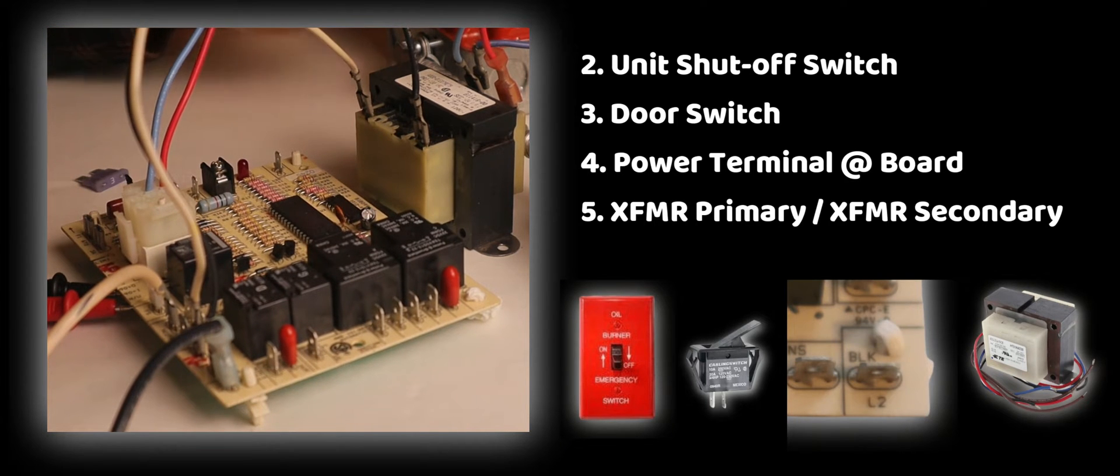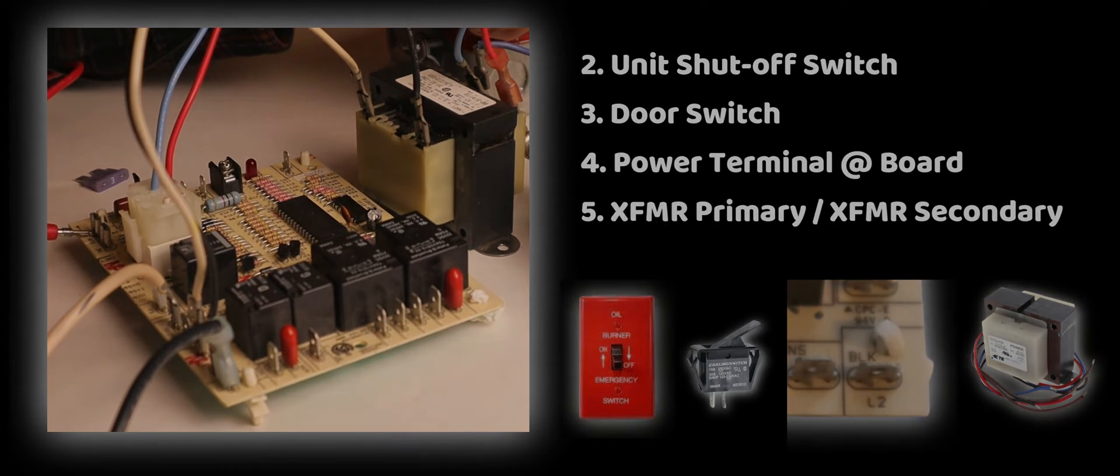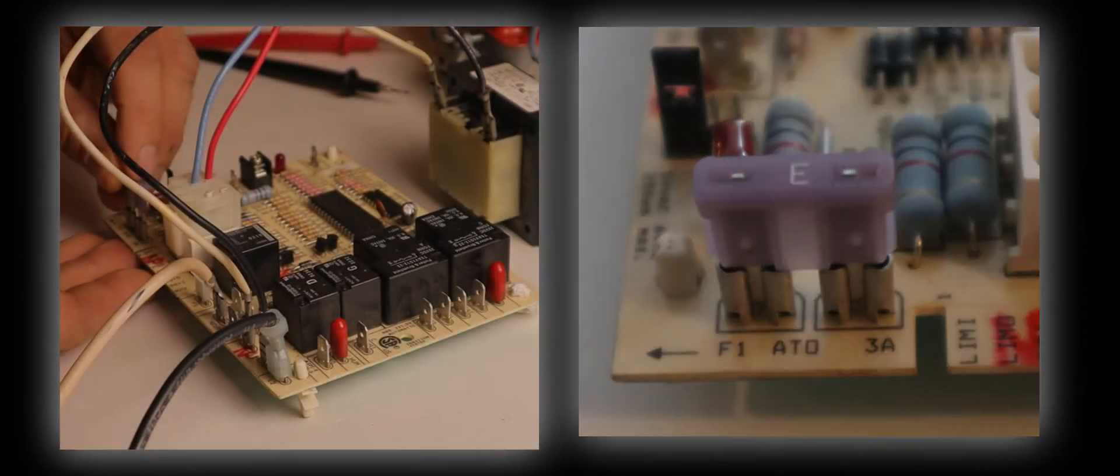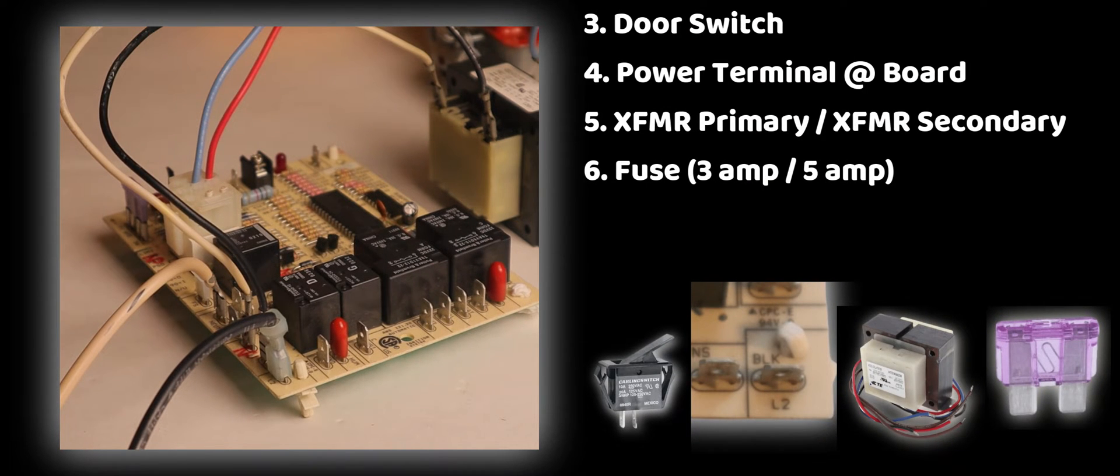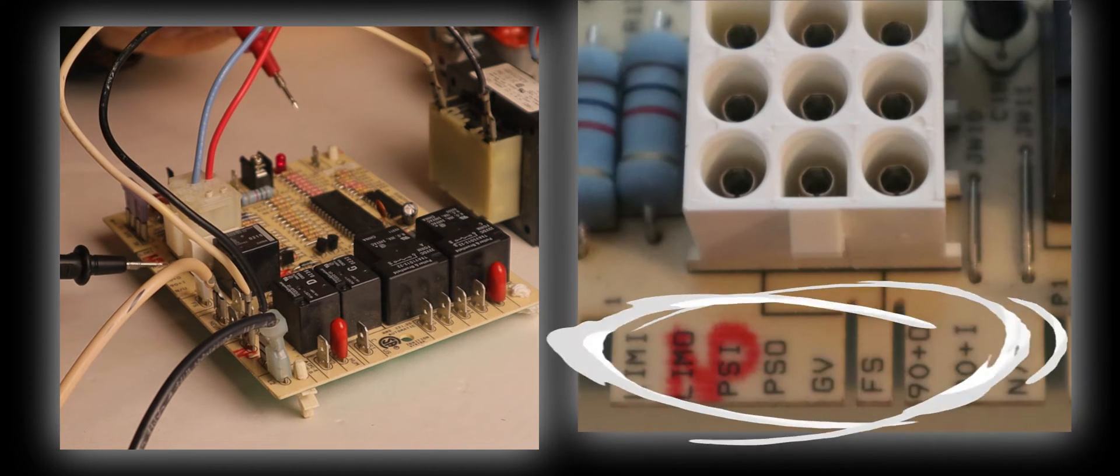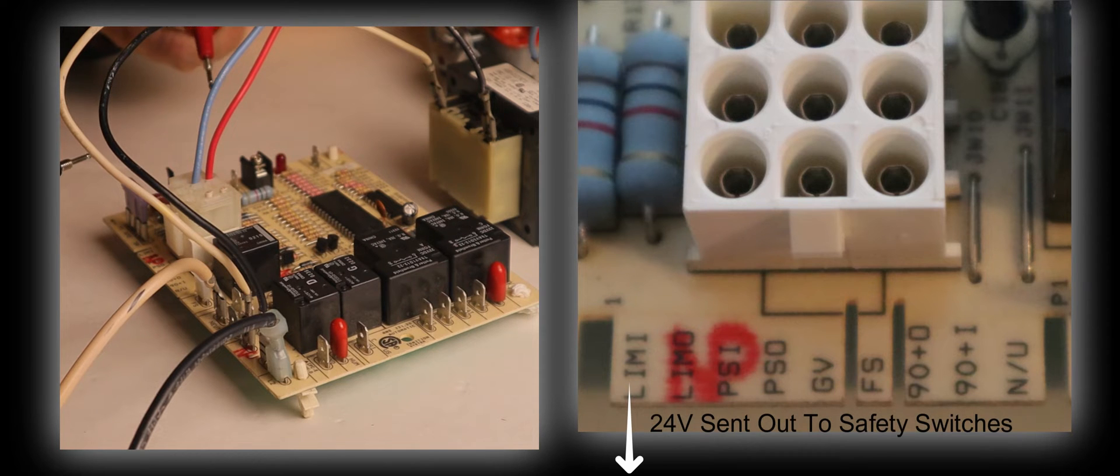I'm now going to put power on it and the only place I have power now is on the inlet to where the three or five amp fuse goes into the control board. I have my power back off, I'm going to put my three amp fuse back into the board. I'm going to restore power and the one place I have power now from the fuse is in a section of the board labeled L-I-M-I, which means limit input. That is a 24 volt signal that goes out to limit switches.